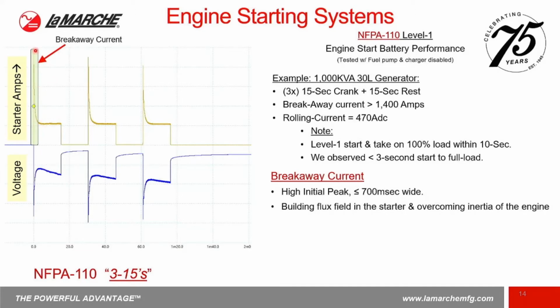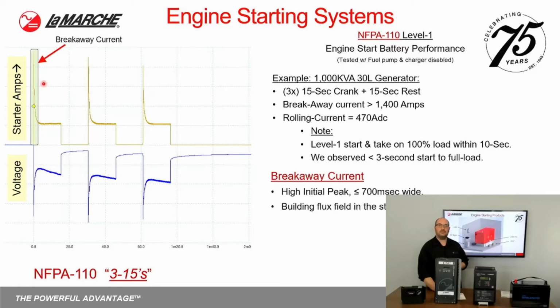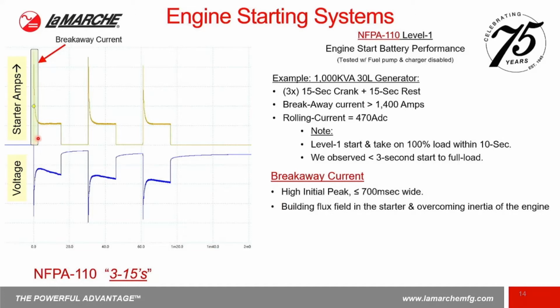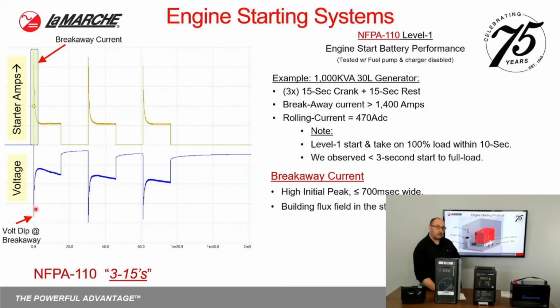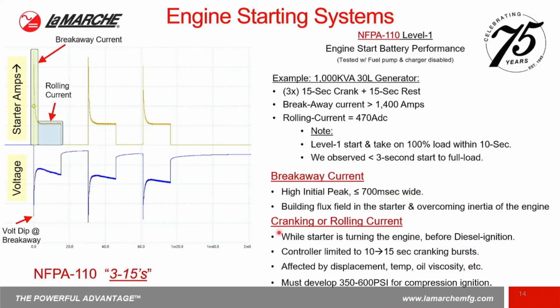You'll notice that it's a fast rising edge, and in this instance, it gets to over 1,400 amps. And it's very narrow. Typically, this is there and gone in less than 700 milliseconds. What constitutes this high leading edge is building flux in the motor and overcoming the beginning inertia of turning over that engine. When there's a high spike of current, there's a large momentary dip in the voltage on the battery system. The next portion is considered a rolling current, or some people call it cranking current.